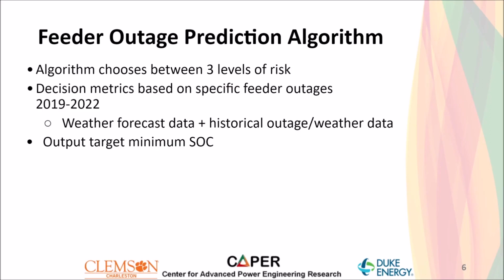And to explain how the feeder outage prediction algorithm works, it's going to choose between 3 levels of risk. There's going to be a flowchart coming up soon that I can walk through. But the decision metrics for this are based on specific feeder outages, looking at a sample case from Duke Energy over the period of 2019 to 2022, identifying the weather patterns that were most likely correlated to the outages that occurred.